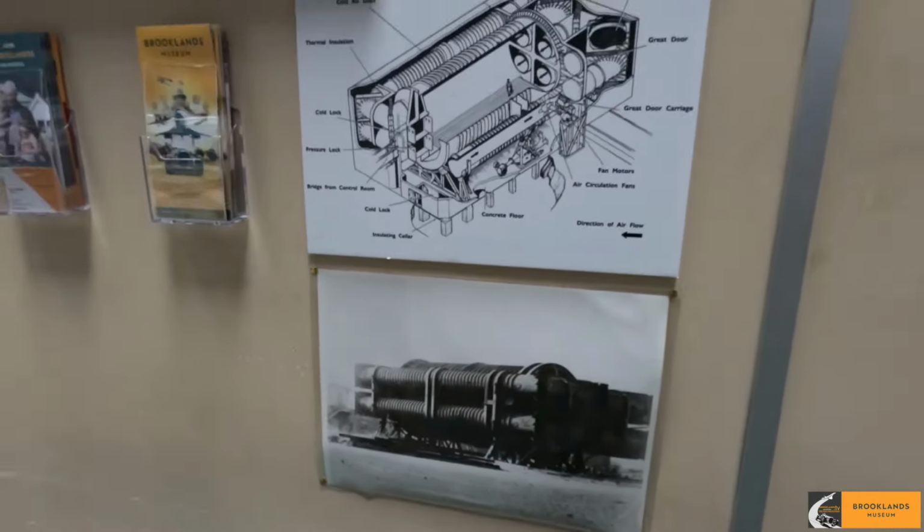So it's hidden slightly underneath the education centre, but it goes all the way round. What this was is an isolation gap for the mount where they put the compressors. There are very deep foundations here, and you've got extremely vibrating equipment on it, four lots of compressors and your vacuum pumps. So they needed to isolate all that vibration from the main part of the chamber. This slot had been put in to actually provide that isolation gap.